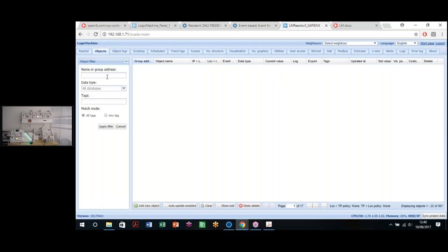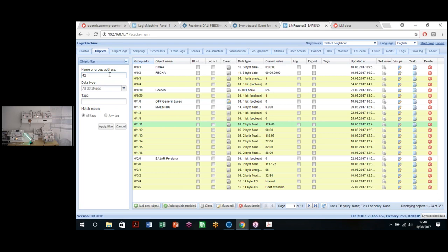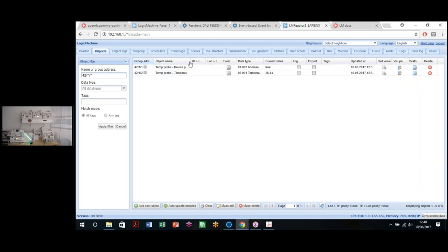So if we go to the objects and we filter for 42, there we go. We have the device is present, the object is true, and the temperature is 28.4375. We can also create events for these objects, and we can create all the logic and all the visualization that we need using these devices, or send it to any other protocol or device, for example Modbus. If we need this temperature from one-wire to be sent to a Modbus device, it's very easy. We just link this one to the other one, and very easily we have intercommunication between systems. So this is one-wire, very easy, very simple to configure.